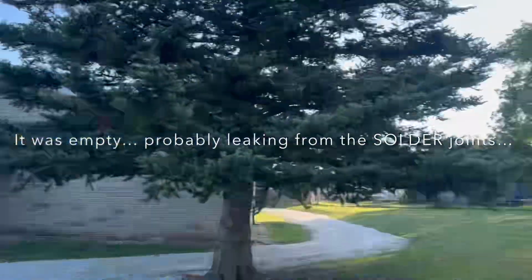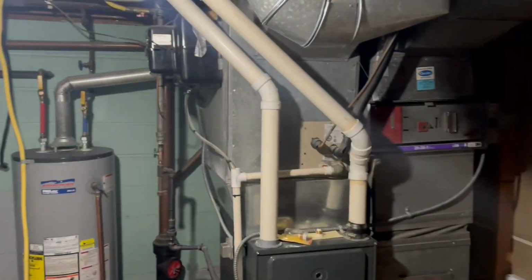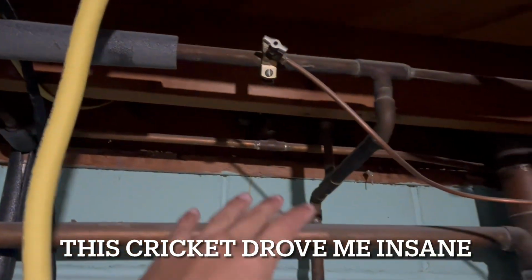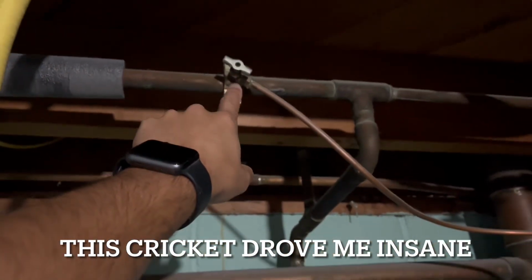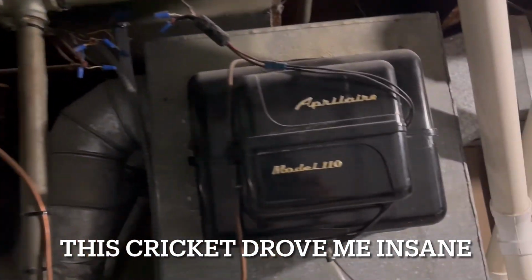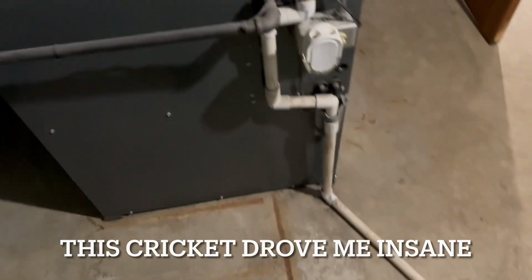Give her the old pump down action. Okay, we got an uncased coil, changing it to a cased coil. We're removing this humidifier. And we all know this saddle valve is just gonna fail. So we're gonna have to figure out something to do about that. But other than that, pretty straightforward.